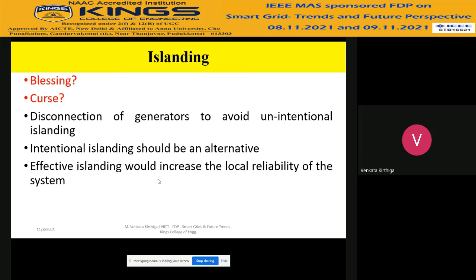Whereas intentional islanding is completely under your control. You can use it for reconfiguration, or if you are generating on par with the load, you can go for intentional islanding and isolate the system whenever you want. Such systems can be operated, and in that case it becomes a blessing.